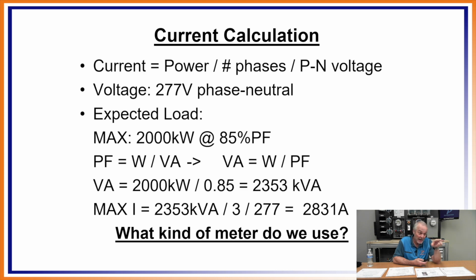Now that I know that, I can say my maximum current, you look at the formula up there at the top: the current equals the power, and we came up with the VA, right? We converted it from the watts to the VA to get our power. And so we've got 2353 kVA, so I got my power, divided by number of phases. This is a three-phase installation, and then it is my phase to neutral, not my phase to phase voltage that I use. So when I do all of that, I end up with 2,831 amps available there, max.